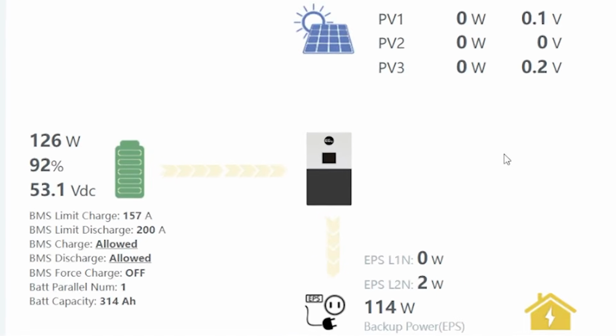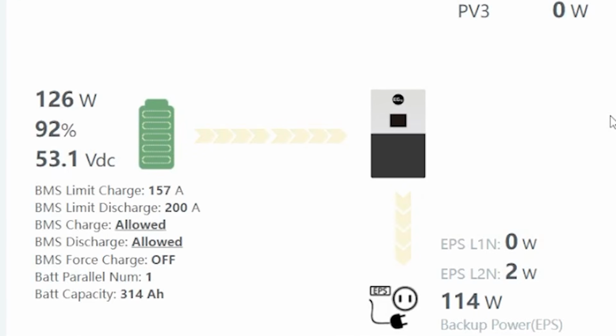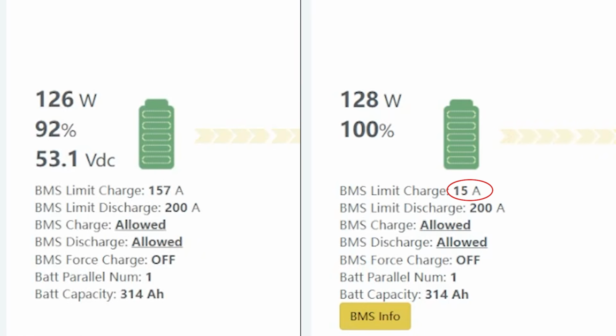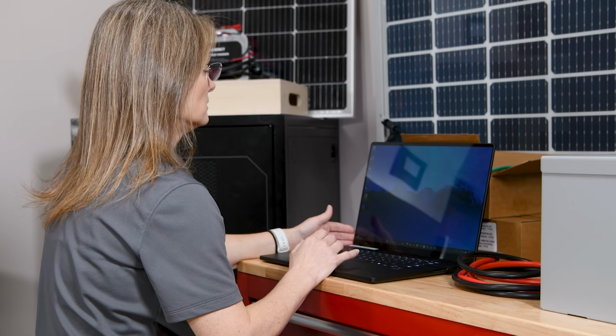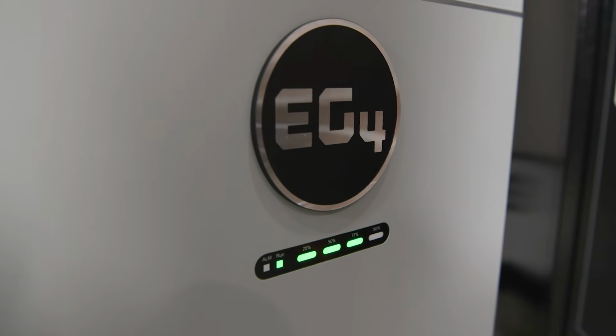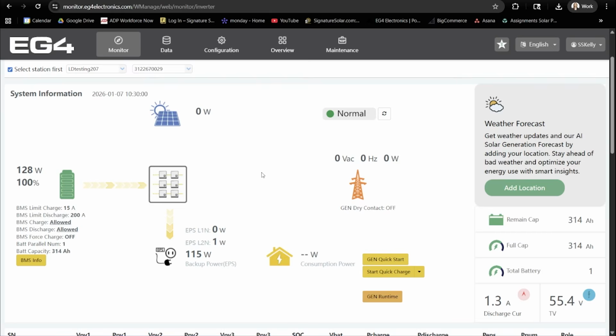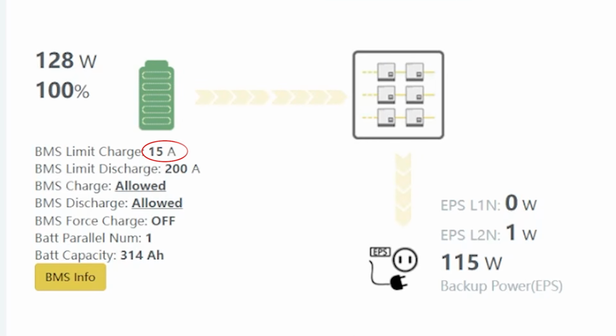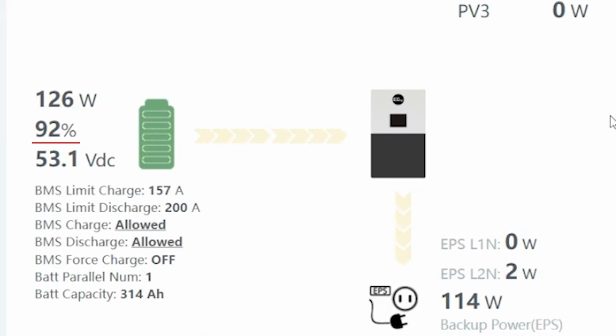One last thing to note is the BMS charge limit. The rated charge limit for the wall mount 314 amp hour battery is 157 amps. But if you see a lower value after the update, that can still be normal. As the battery approaches a high state of charge, the BMS will reduce current charging to protect the battery from overcharging. When I performed this update with the battery already at 100% state of charge, my BMS charge limit was showing around 15 amps, which initially concerned me. As I discharged the battery, the charge limit increased again, which is expected behavior.